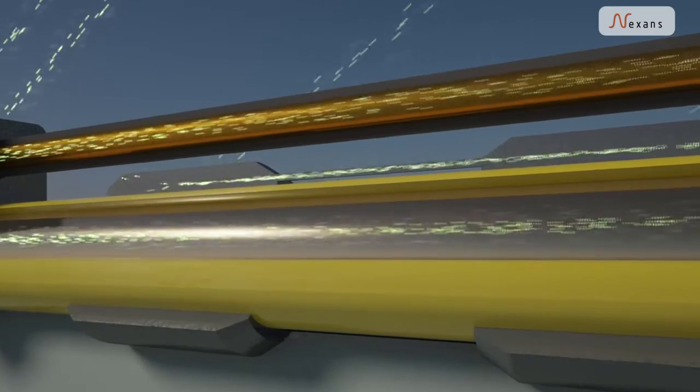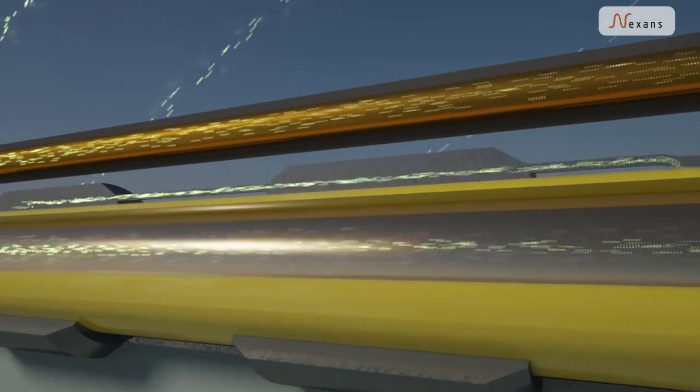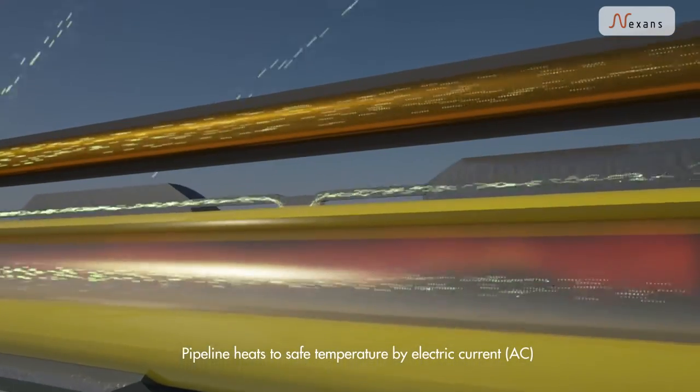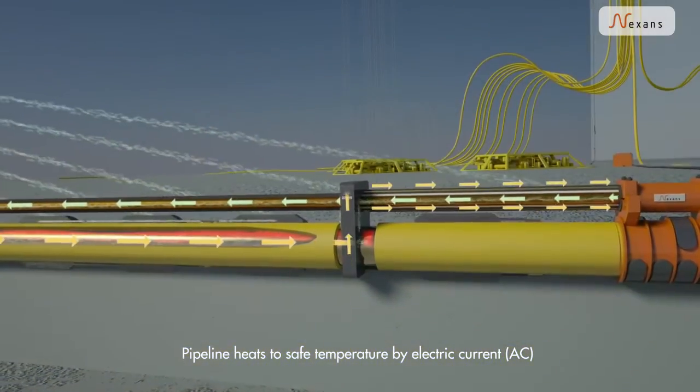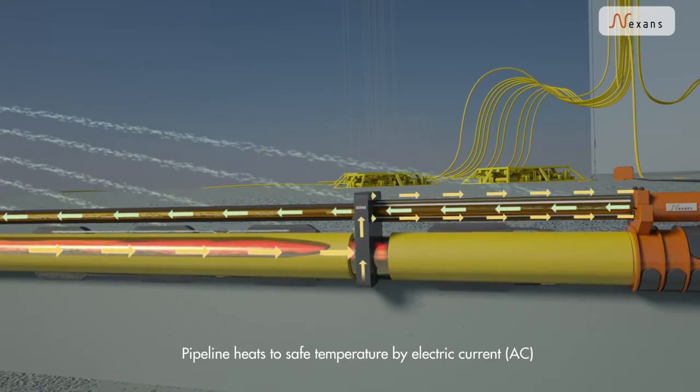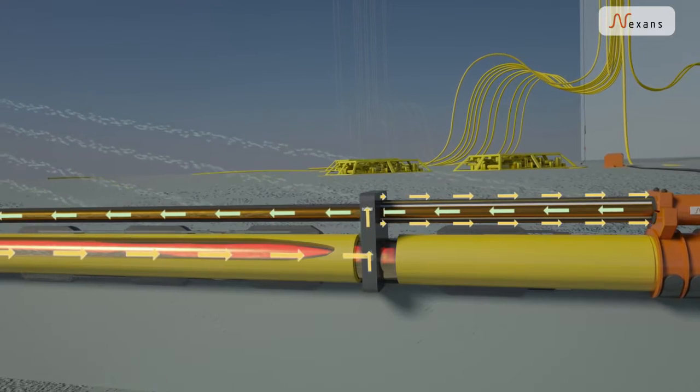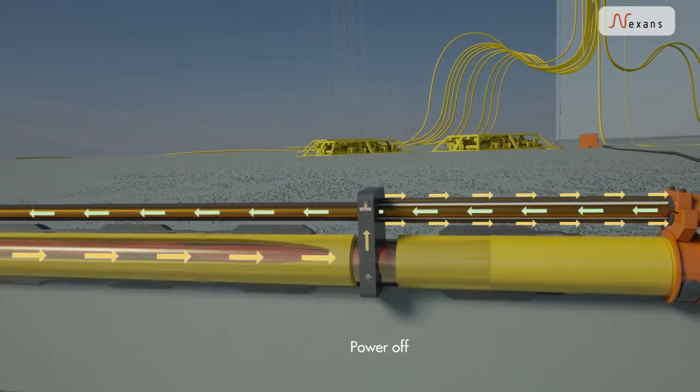Some of the current is allowed to escape through the anodes into the seawater in a controlled manner. At the near end, the currents rejoin the pipeline and return via the riser cable outer element.